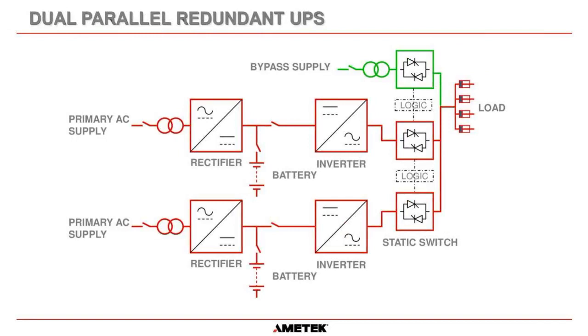And then we have parallel redundant systems without any diesel generator, and this is a parallel redundant system. And what you will see is everything in red is energized and supplying load, and everything in green is just energized. So both UPSs, let's say this is UPS A and this is UPS B, they are connected together at this point here. Now, for simplification, I've drawn it without a remote manual bypass switch, but both UPSs are connected together, and they have logic between them that shares the load, and so they know what each system is doing. So, for example, if the inverter in UPS B fails completely, then UPS A will continue supplying all of the load without any issues whatsoever, and the static switch will know that UPS B has failed, and it will not try to switch UPS B on until it knows B is healthy again.